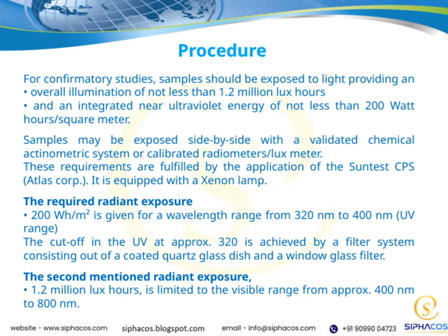To achieve these conditions, samples can be exposed side by side with a validated chemical actinometric system, or using calibrated radiometers or lux meters. This ensures precise measurement and control of the light exposure. A common tool used for this purpose is the Suntest CPS from Atlas Corp, which is equipped with a xenon lamp.